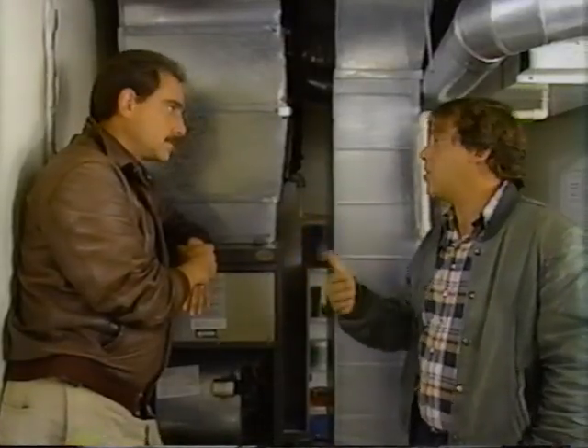You can also look at baseboard electric heat, which are slightly smaller toasters distributed throughout your house. Well, it seems to me that baseboards, if they work the same, would be a lot easier to install than a lot of ductwork and stuff. Fair enough. Builders are always looking for the lowest upfront installed cost on things, but you've got to realize that in this type of housing, we are looking to distribute fresh air to all the rooms in the house. So if you're going to put in an electric baseboard heating system, you are also going to have to duct fresh air to the rooms in the building.